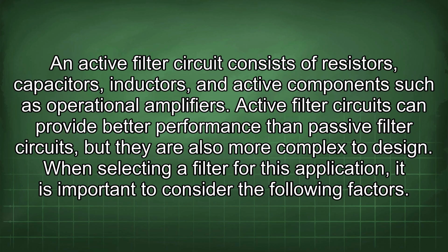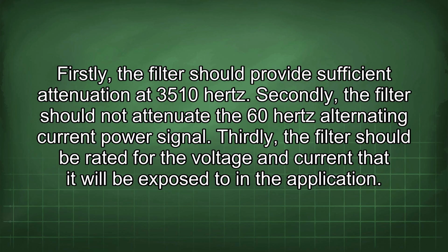When selecting a filter for this application, it is important to consider the following factors. Firstly, the filter should provide sufficient attenuation at 3510 Hz. Secondly, the filter should not attenuate the 60 Hz alternating current power signal. Thirdly, the filter should be rated for the voltage and current that it will be exposed to in the application.